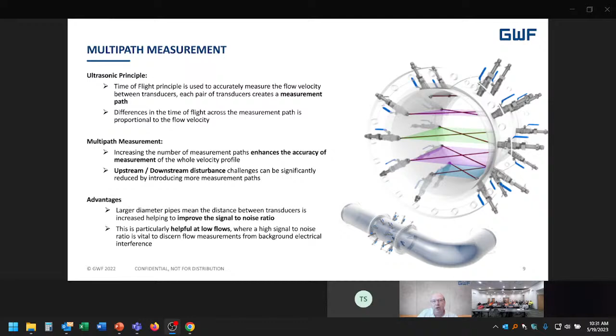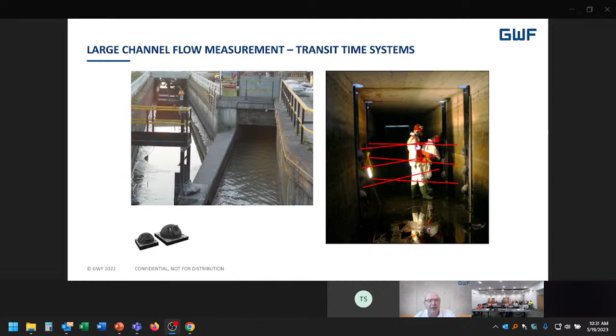Taking that idea of multi-path, multi-layer applications, we can use it instead to look at, say, a channel flow measurement or tunnel flow measurement. Again, with transit time, we're sending signals from one side to another. We're creating planes or layers of two-path measurement so that we can accurately measure through a channel, a canal or a tunnel. These types of applications, whether it be a raw water intake, we've actually seen in Mexico City, where they've recently installed a similar system with 3 layers to measure the raw water intake into their largest treatment plant that they have for the city.